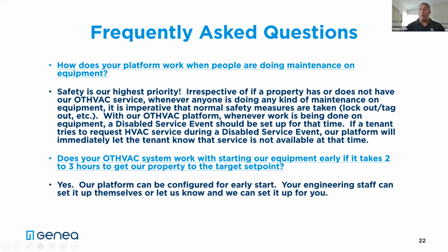How does our system work when people are doing maintenance? Safety is obviously a big deal, so from a building perspective, you're going to do your own standard lockout, tagout. What we do is we have maintenance requests that we can put in the system. So if you're telling us you're going to do maintenance this weekend on, say, the first five floors of the building on their air handlers and fans, we'll put in a maintenance notification in the system so nobody can make a request, and it'll just notify to contact building management when service is ready again.